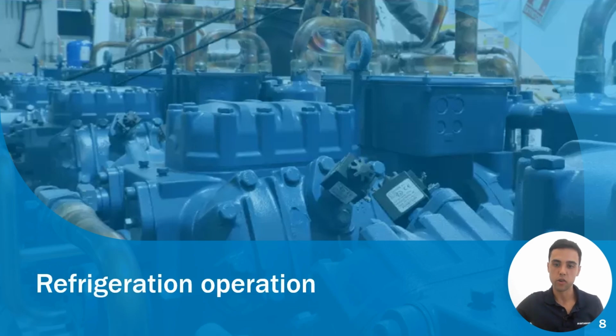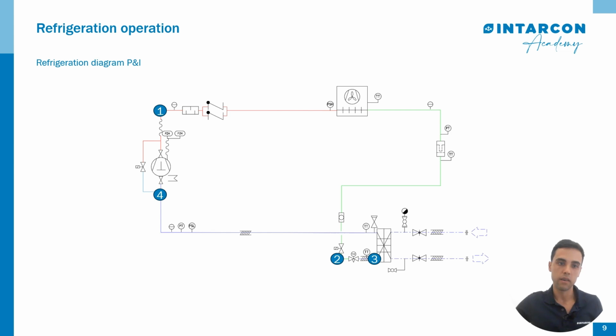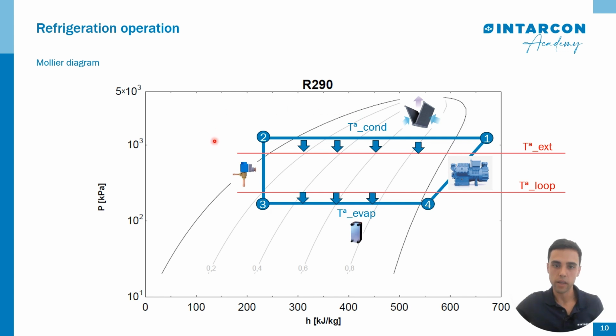Now let's see the refrigeration operation. In this slide we can see the refrigeration diagram, the P&ID diagram. The compressor sucks gas and compresses it to a high temperature and pressure, which is condensed in the microchannel condenser, expands in the electronic expansion valve, and exchanges the heat in the plate. We also see here in the Mollier diagram where the condenser exchanges heat with the air environment, and we also exchange heat in the glycol loop with the refrigerant circuit.